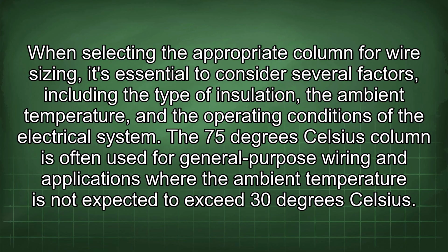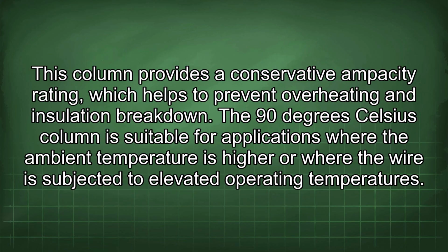The 75 degrees Celsius column is often used for general-purpose wiring and applications where the ambient temperature is not expected to exceed 30 degrees Celsius. This column provides a conservative ampacity rating, which helps to prevent overheating and insulation breakdown. The 90 degrees Celsius column is suitable for applications where the ambient temperature is higher or where the wire is subjected to elevated operating temperatures.